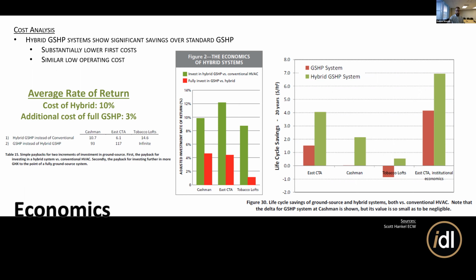In one of these cases, the tobacco lofts, there was no payback for the ground source heat pump, not after 20 years. It might have been operating more efficiently, but over the lifespan, it still cost too much upfront to make that money back. At Cashman, it turned out to be about even. But for every single one of these sites, the hybrid system did end up with a significant 20-year savings in terms of dollars per square foot.